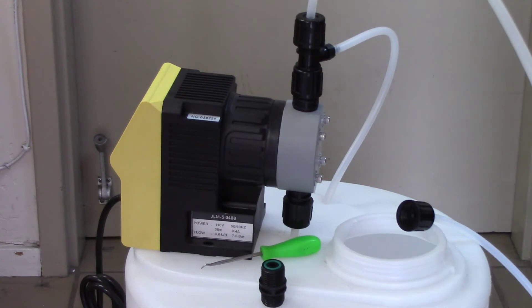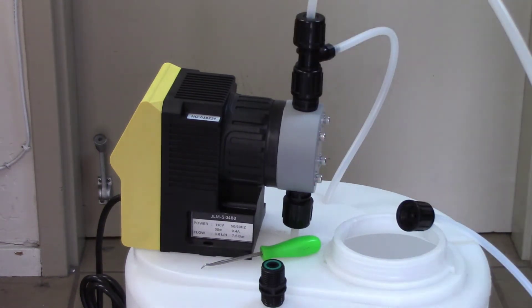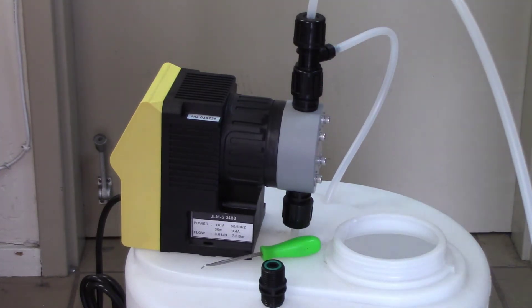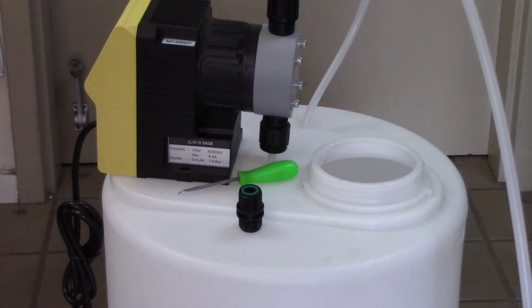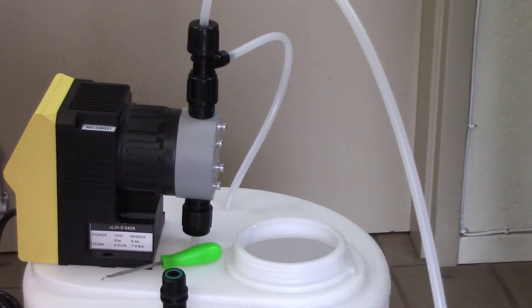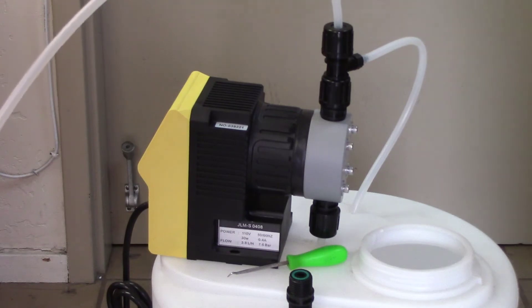One set goes in the bottom, one set goes in the top. This might get salted up or needs to be cleaned off, and that would be the inlet/outlet and the foot valve fittings. If you think that's what's happening, then you can take all those fittings off and clean them. If it's the foot valve, when the pump is off and you leave it off for a couple of hours, the tubing down in the tank - you should start seeing an air bubble, telling you the foot valve is not holding and the water's back feeding into the tank. But when the water level is rising in the tank, that's indicating that it's back feeding, getting water from your source, which indicates that the injection check valve is failing.